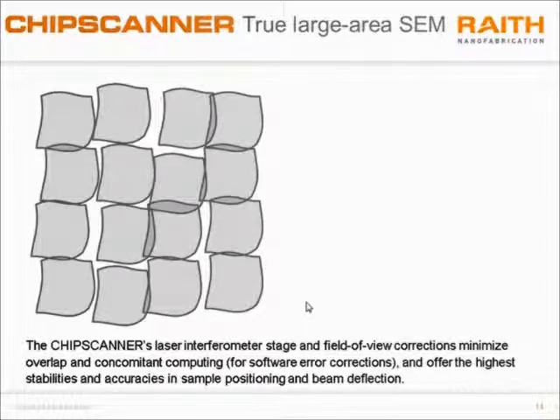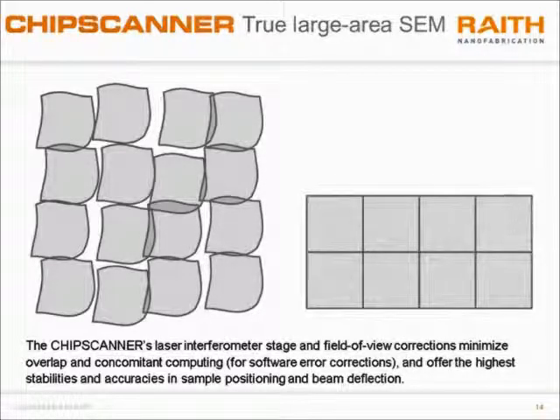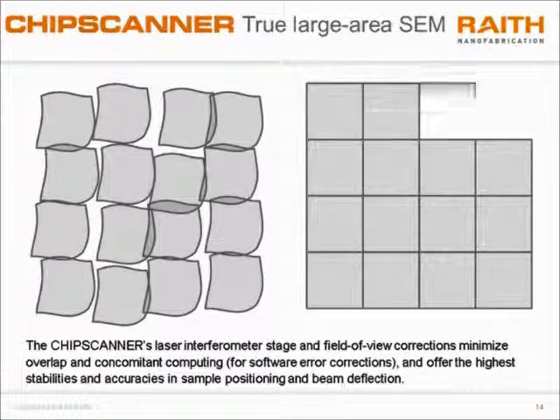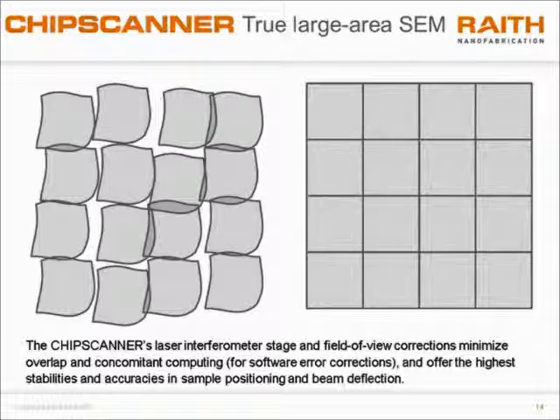So, with the chip scanner, we have a calibrated field of view. The laser interferometer stage is used to calibrate the field of view, measuring and mapping out all of the distortions. And then this accurate field of view can be stepped with a very accurate laser interferometer stage, and these images can be stitched together. Also, the overlaps between the images can be minimized, and this really improves the overall speed of the chip scanner compared to a traditional scanning electron microscope.